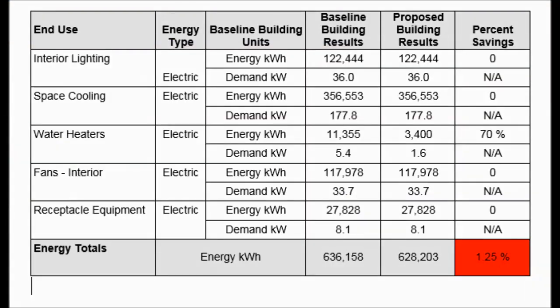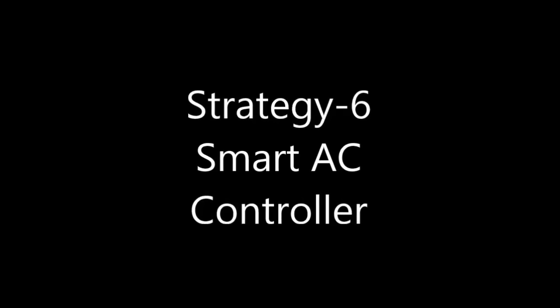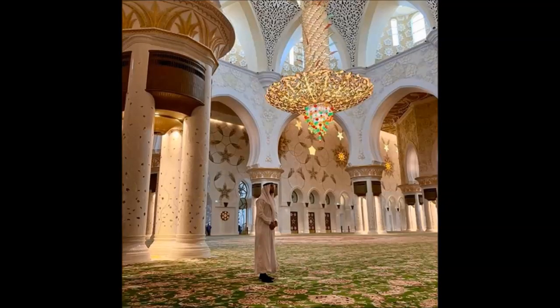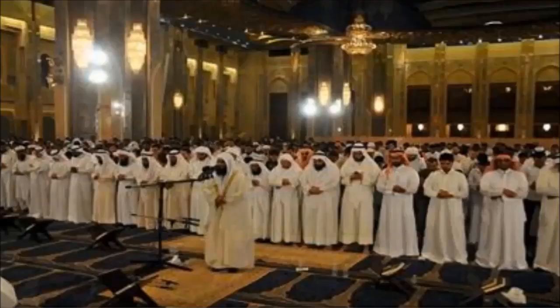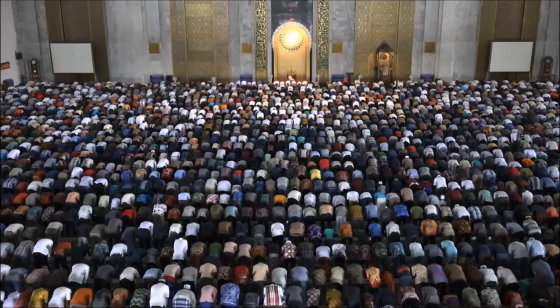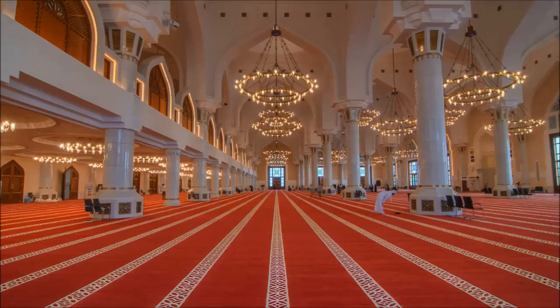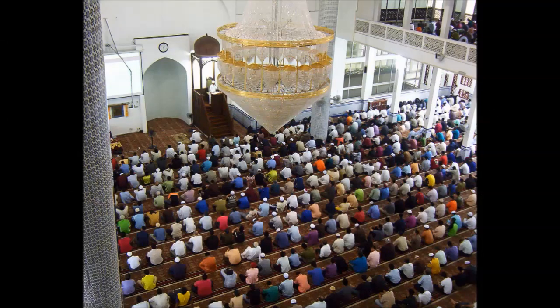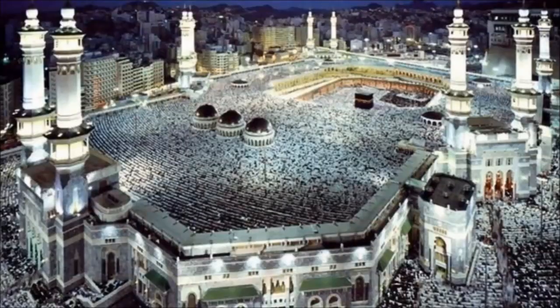Adding a solar water heater will lower the total energy of the building by a value of 1.25%. Mosques are different from any other building. The pattern of use of mosques is quite unique. For example, the mosque is probably empty during the day, except for the 5 prayer times where it experiences sudden populations. This higher population can last for 15 to 20 minutes, then it will be empty again. Moreover, mosques experience a much higher population on Friday prayers than any other day, and in Ramadan than any other month.